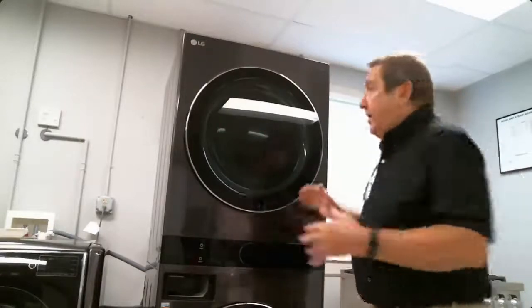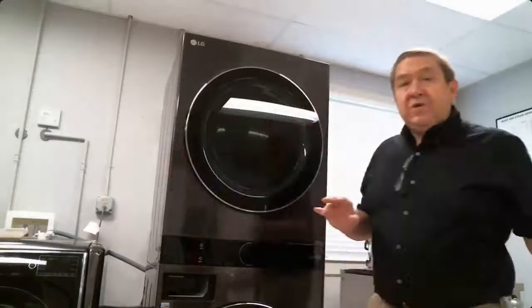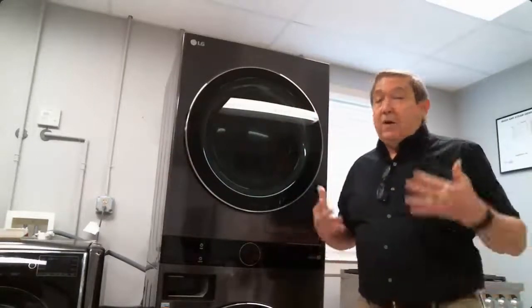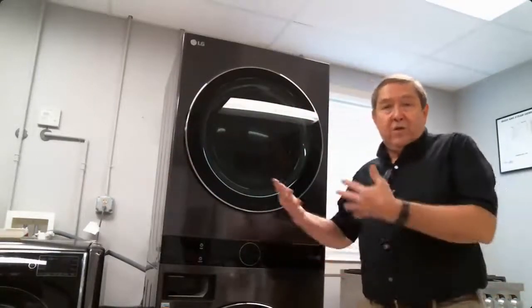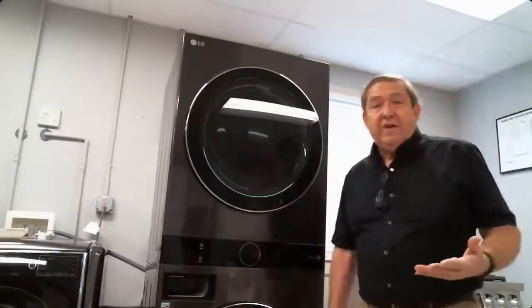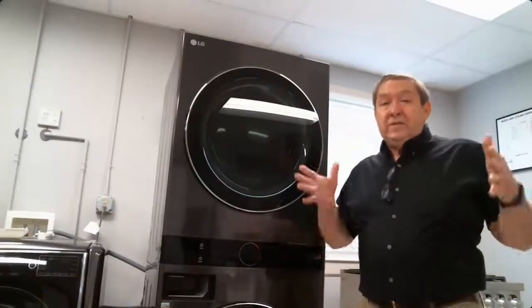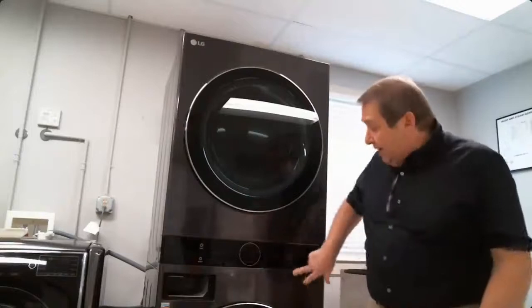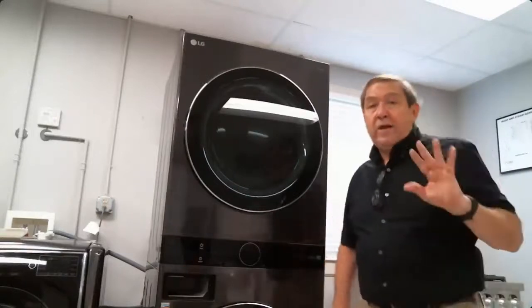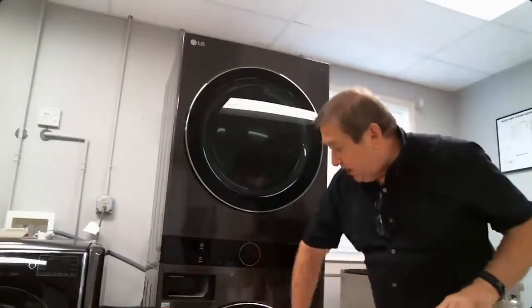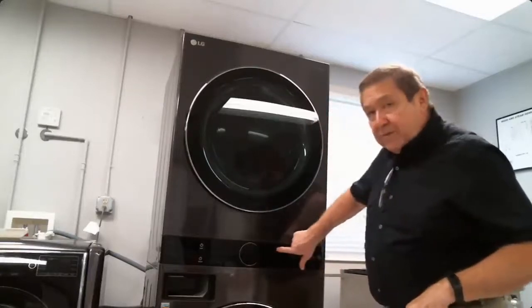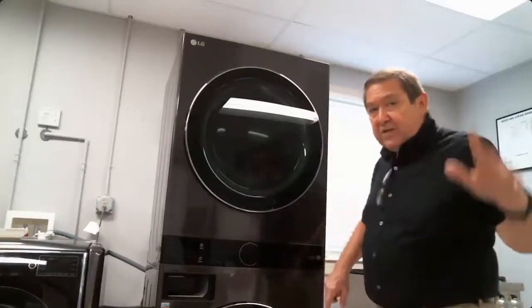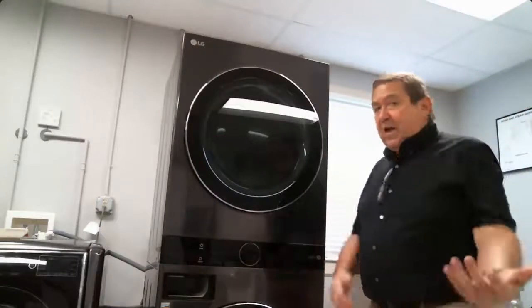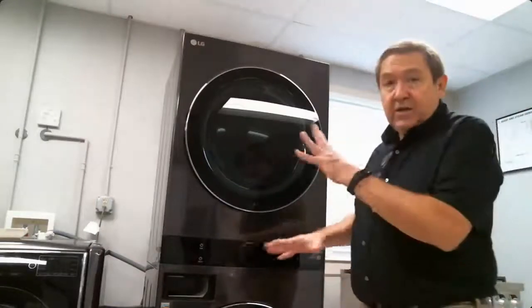And this will sound, guys, just like a bad bearing. This thing will be roaring, this thing will be shaking. Customer says it doesn't spin like it used to, and you'll swear you've got a bearing job, but when you take it apart, there's no evidence that water's ever been leaking. So really suspect your Hall sensor at that point, and that's one way to quickly check that, because if that thing is spinning, I should be seeing RPMs on the screen. If I'm only seeing 0 on there, then that gives you an indication I'm not getting a signal back, and this thing doesn't know how to control that at that point.